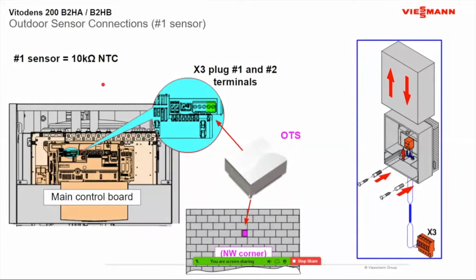Your outdoor sensor, I always like to mention this because, being a former tech support person, believe it or not, this was a common problem: the location of your outdoor sensor. It is a 10,000 ohm NTC resistor inside here, and we do have charts in the manual. I actually have troubleshooting on these as well if you go into the videos. But we want to see our outdoor sensor on the northwest side, the coldest side of the building. Don't want to see them under a dryer vent, which is kind of common, and exhaust vents that we just drilled out that new hole so we can get our thermostat wire out there as well, and then hang our outdoor sensor right under the exhaust. So we want to make sure we're away from any exhaust and any sunlight that would fool it into thinking that it's warmer than it actually is outside. So you'll get the calls, and it can be a headache if it's located on the wrong side if you're going to do outdoor reset.